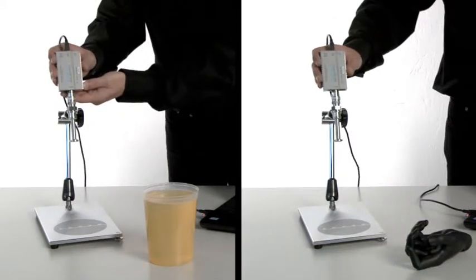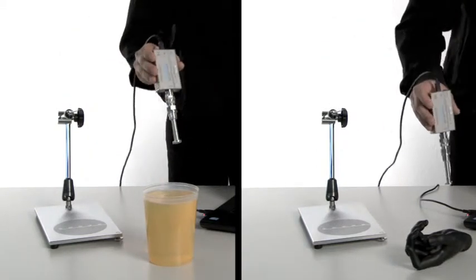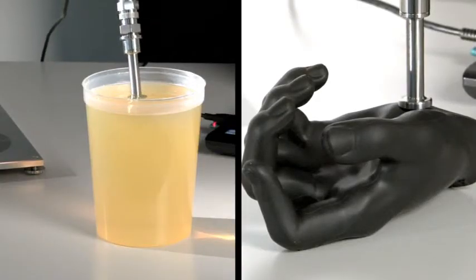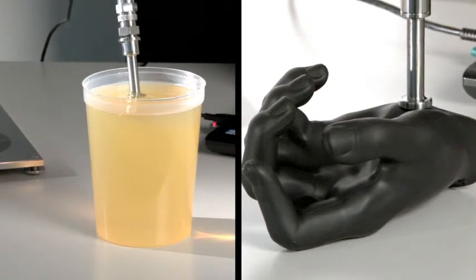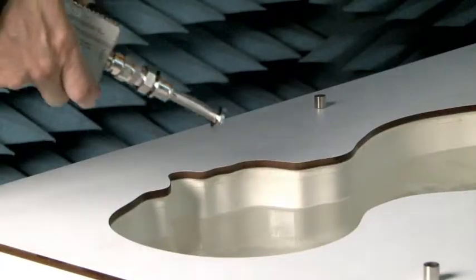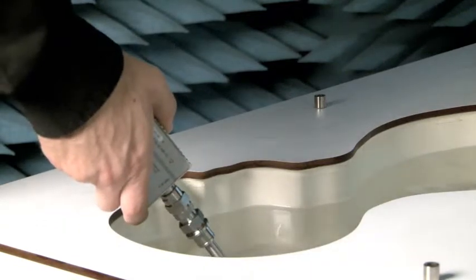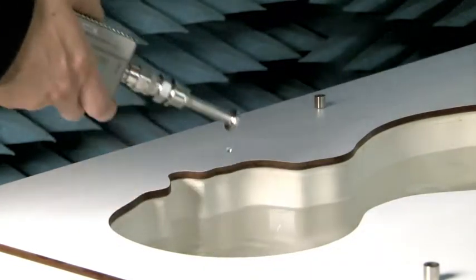For details of a precise calibration, please watch the DAK tutorial movie. Once the calibration is finished, take the system from the probe stand and move it to the material under test. For example, you can validate the tissue simulating liquid already prepared for SAR measurement.